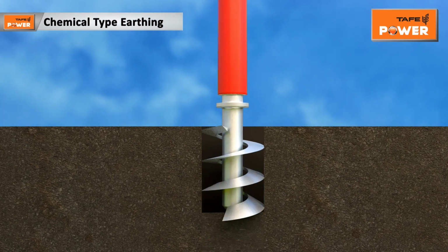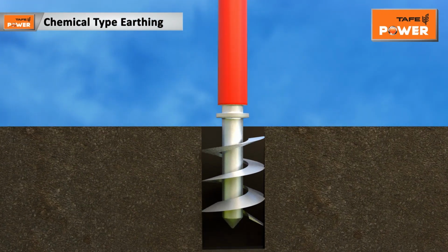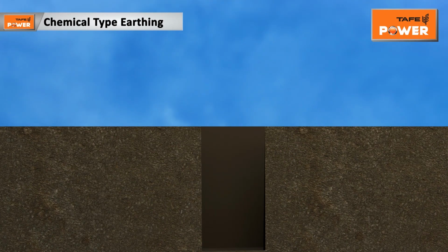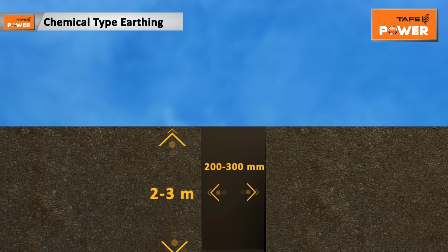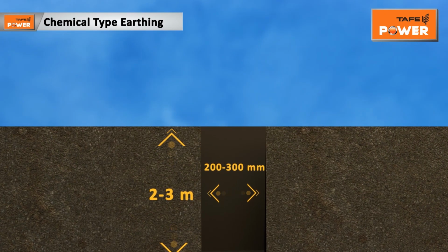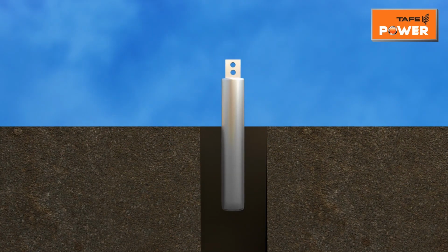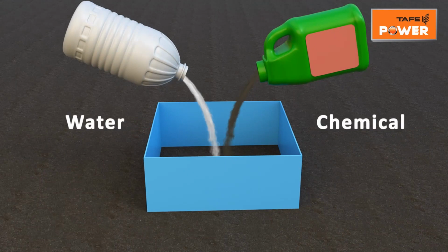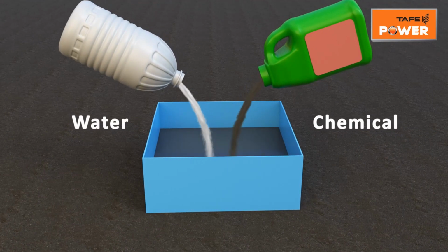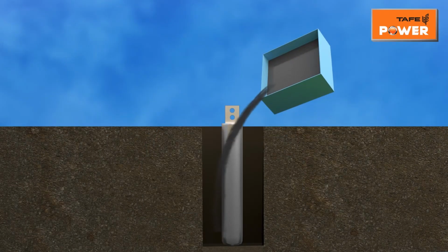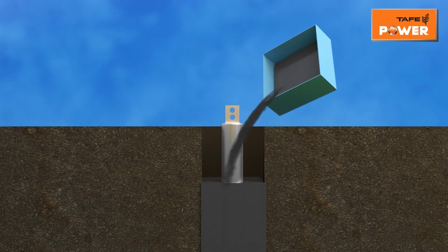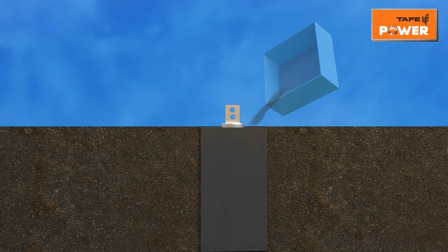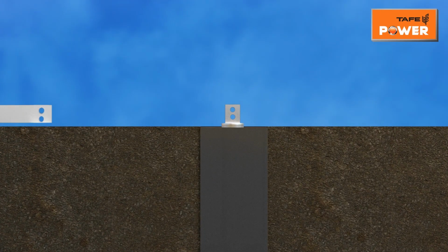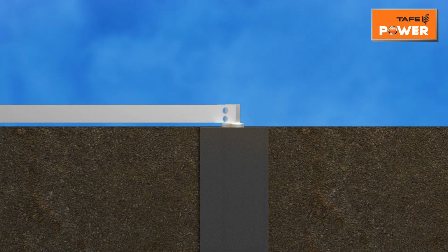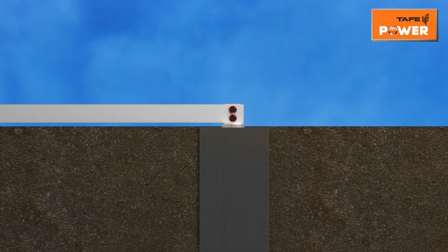Dig a hole on earth of 200 to 300 millimeters diameter up to 2 to 3 meters in depth according to the length of the electrode so that the connection terminal should remain above the ground level. Place earthing electrode at the center of the hole. Mix the chemical compound nicely with water to make a thick and slurry mixture. Pour mixture in surrounding area of electrode gradually to reach up to ground level. Connect earthing strip to electrode terminal firmly using bolts and nuts.